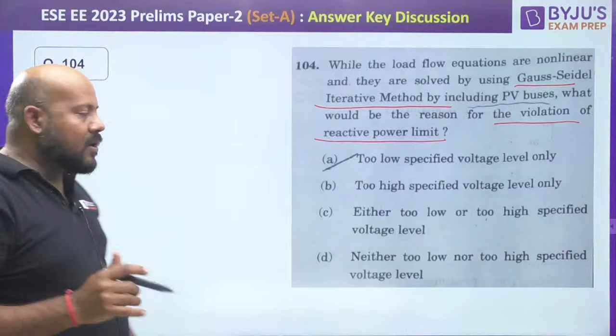You must know that if the reactive power limit is breached, what do you do? Suppose for any bus you get Qi less than Q minimum. For that iteration, you fix the injected reactive power for that bus to the minimum limit, and you treat that PV bus as a PQ bus because you have fixed the Q value.